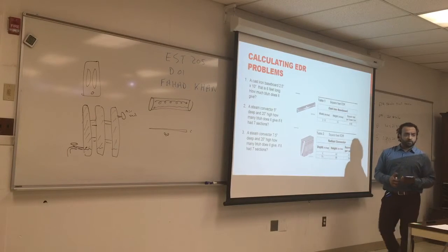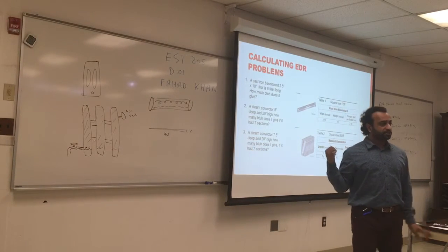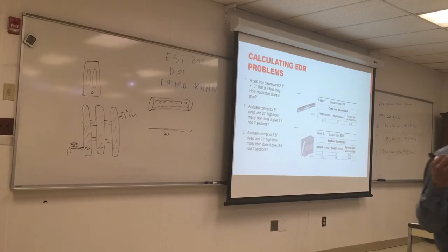Do you notice that there is no temperature for steam? Why is that? Because steam is still going to be at a fixed pressure, which is 2 psi. At a fixed pressure of 2 psi, the temperature is known for the steam, and the volume is just the amount of steam you pump through it. The more steam you pump, the more heat you will get. So steam will convert into water using latent heat.